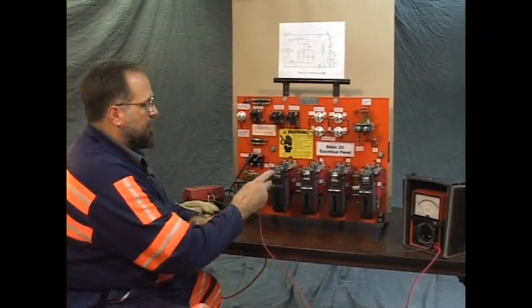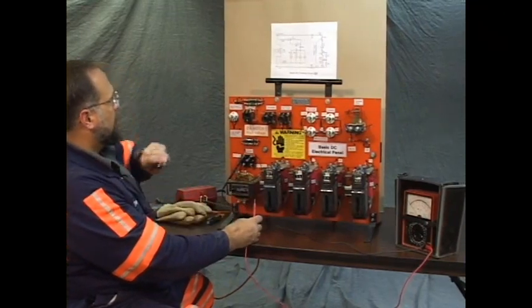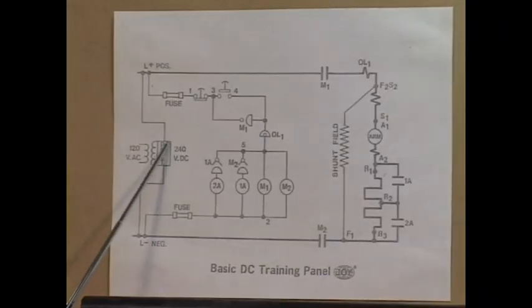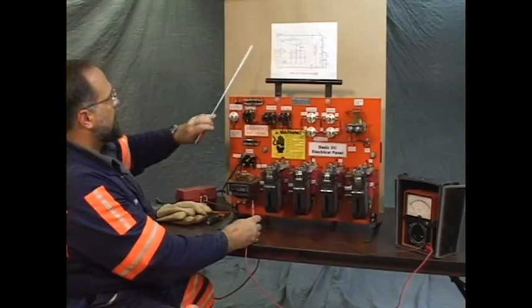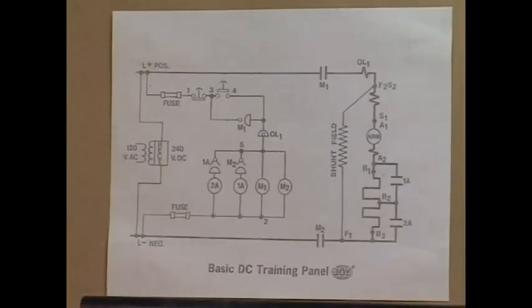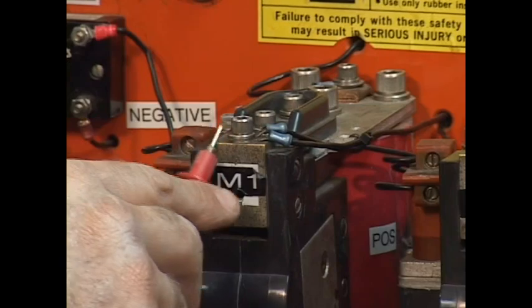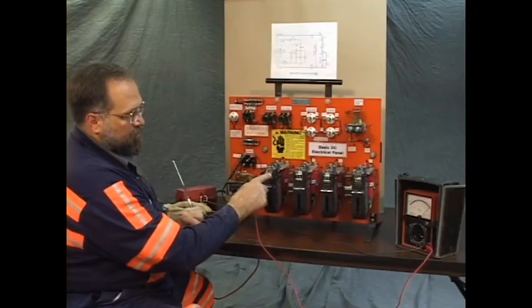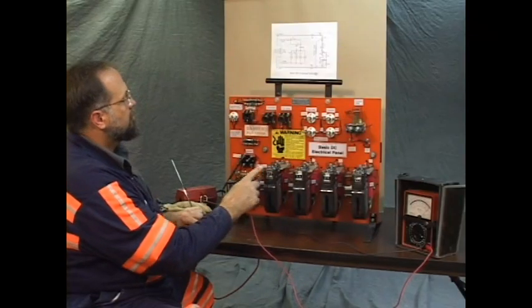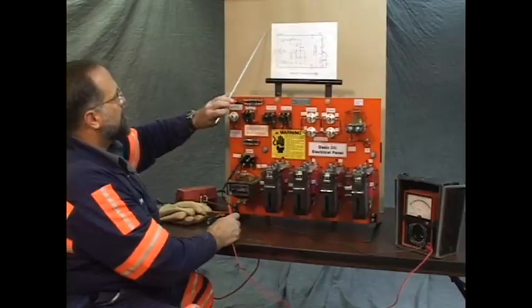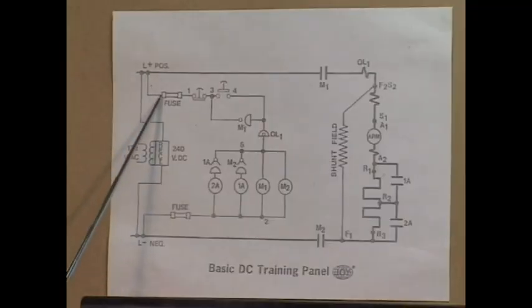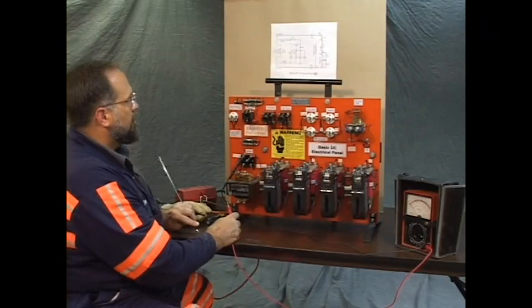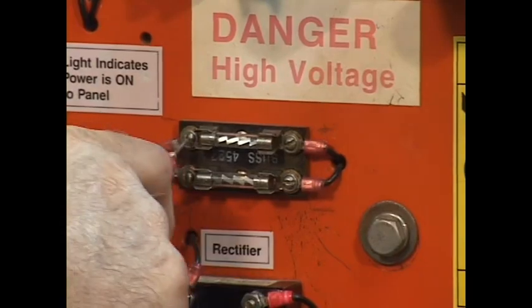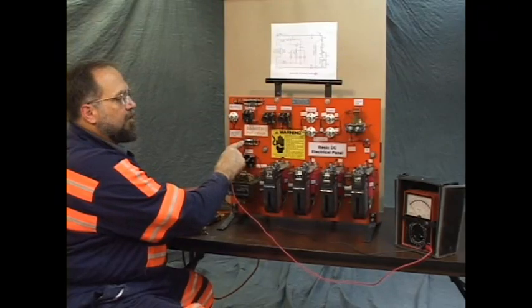The first test I make, I attached a probe right here. The first test I'll make is to the top front of the M1 starter, top front, and that's here. Note the meter reading. We have a good circuit. The next point that goes to is from here, to the line side of the positive fuse. Well then, we don't have a circuit.